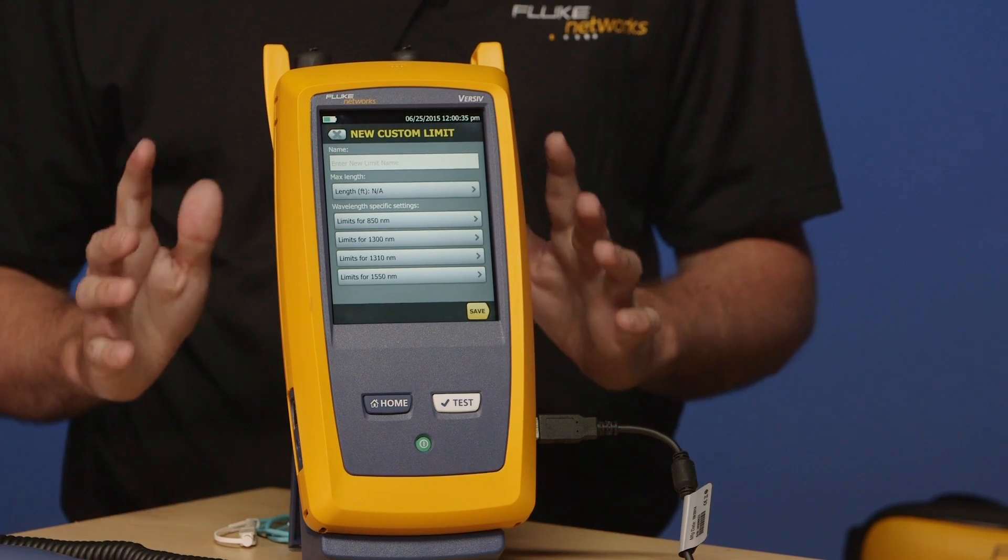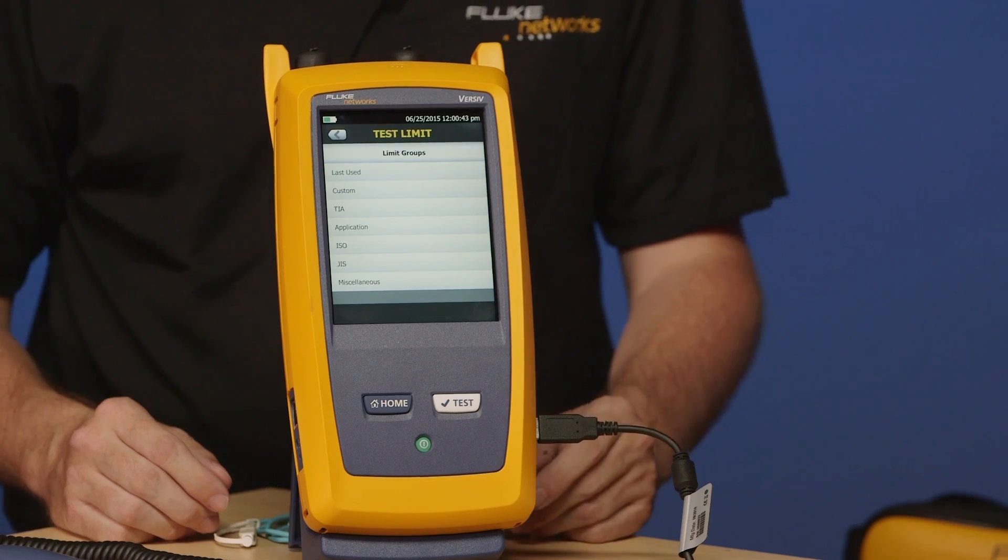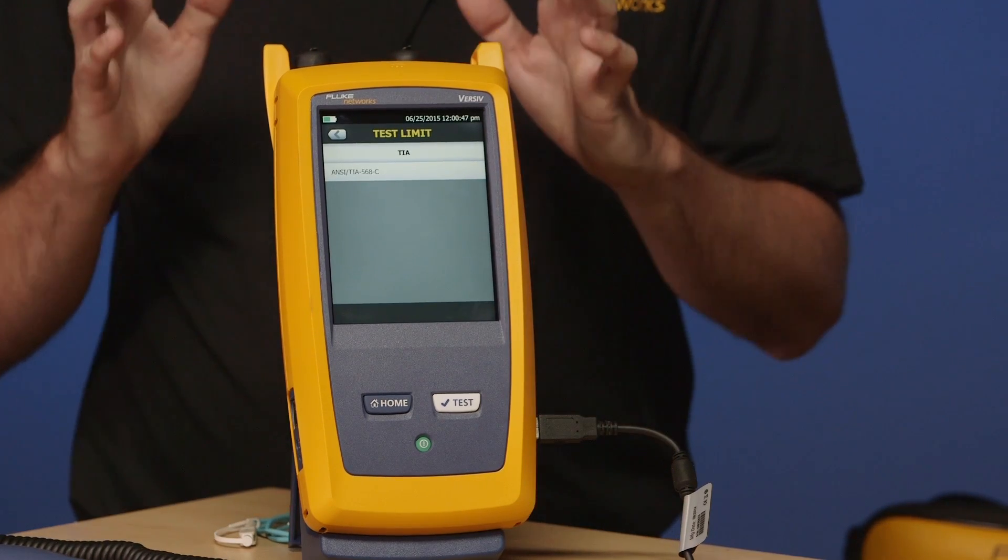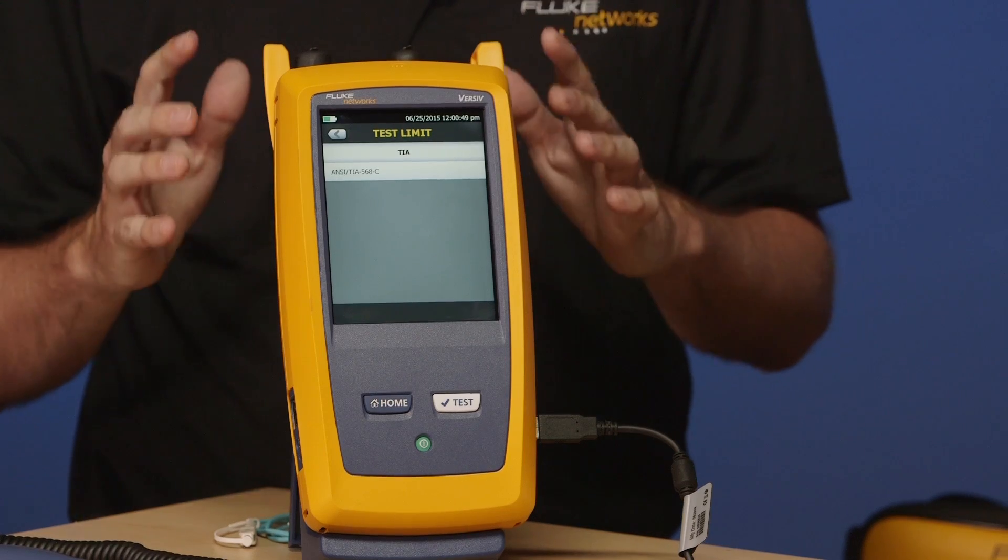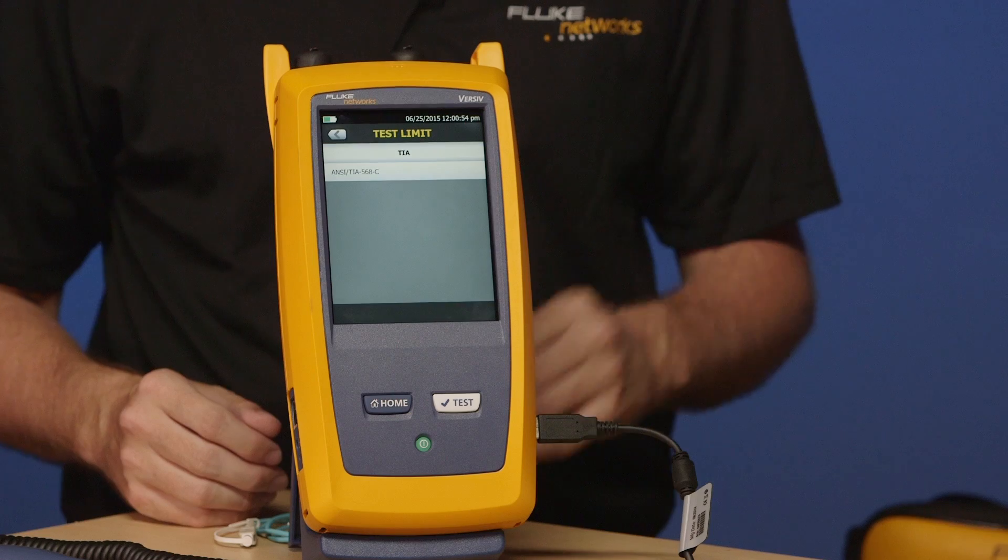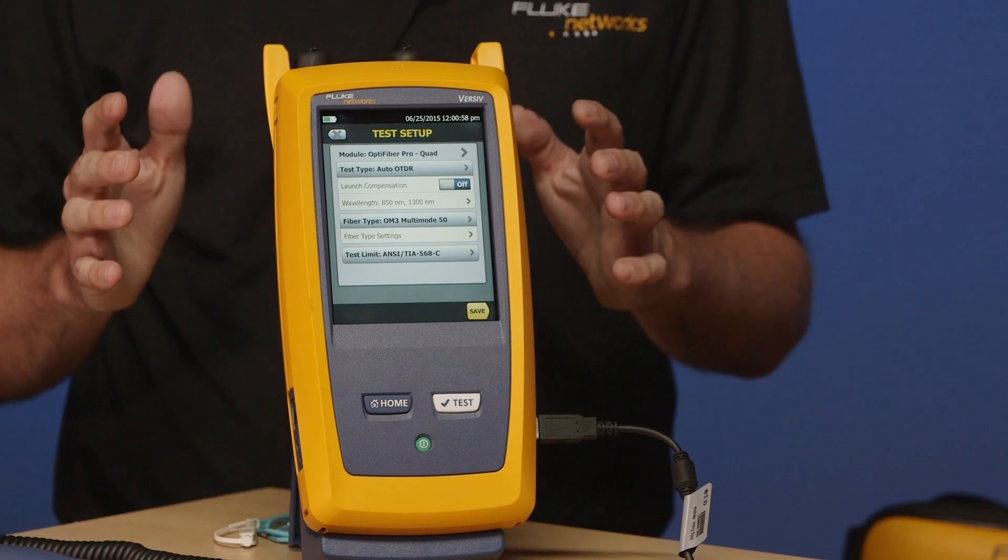We're going to use a basic test today. So, if you'd like to come out of that menu for me. Okay. There we go. And we'll go down to TIA. And we'll select 568. Now, because we selected the fiber type as multimode, our test limits here that we're going to be presented with will be multimode only. So, go ahead and tap that for me. Excellent. And fundamentally, we've just set up the tester now.